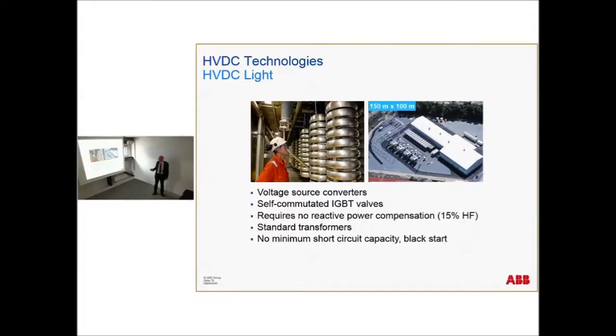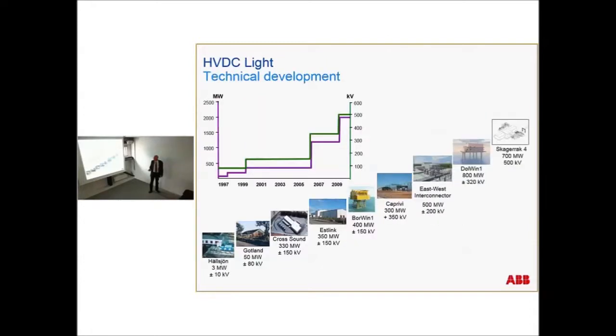Here is a 300-400 megawatt station, and you need a footprint of approximately 100 times 150 meters for such a station. And we see also here the rapid technology development. We started 1997 with the test installation. The first commercial was to the island Gotland in Sweden, 1999. And today we will install 2014-2015 the Skagerrak 4, 700 megawatt at 500 kV.